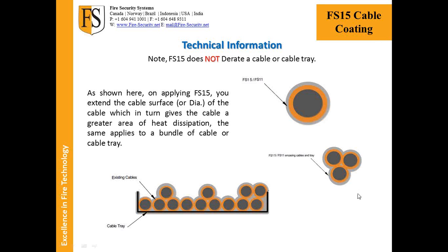Okay. And the same applies for... Sorry, I've got another question. If I look at the cable tray, normally the cables are already in the cable tray, and you spray on top of the cables, basically? Yes. How does the product get in between the cables and to the bottom of the tray? There's no need for it to get in between the cables. Obviously, it appears so in this drawing, but that's just a drawing. All you are doing is effectively spraying all around the surface itself and protecting the surface area from external fire.